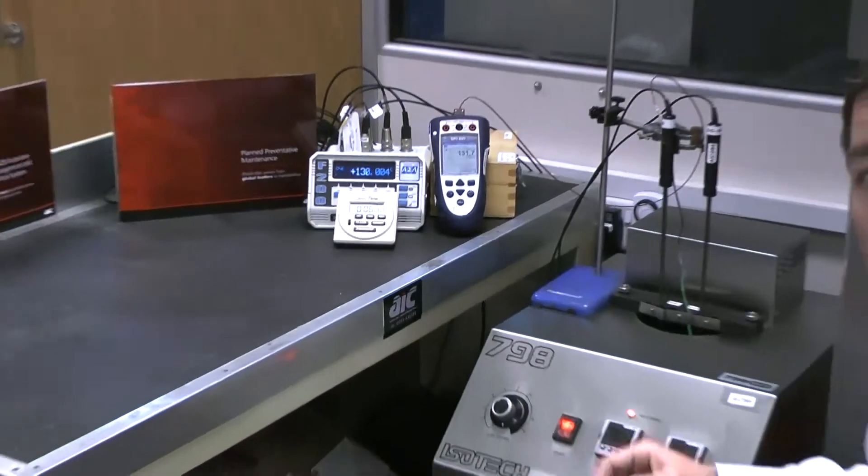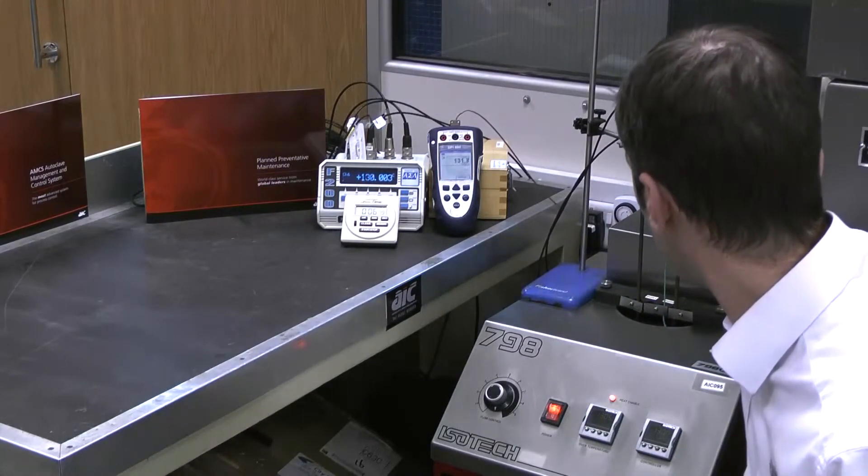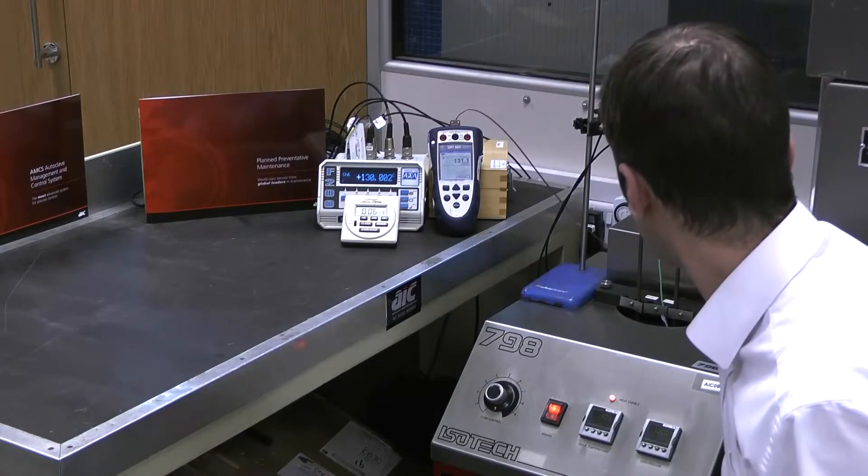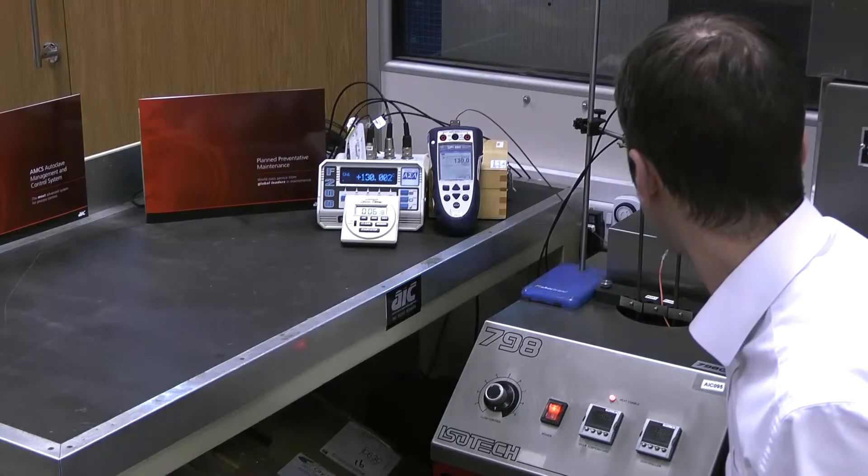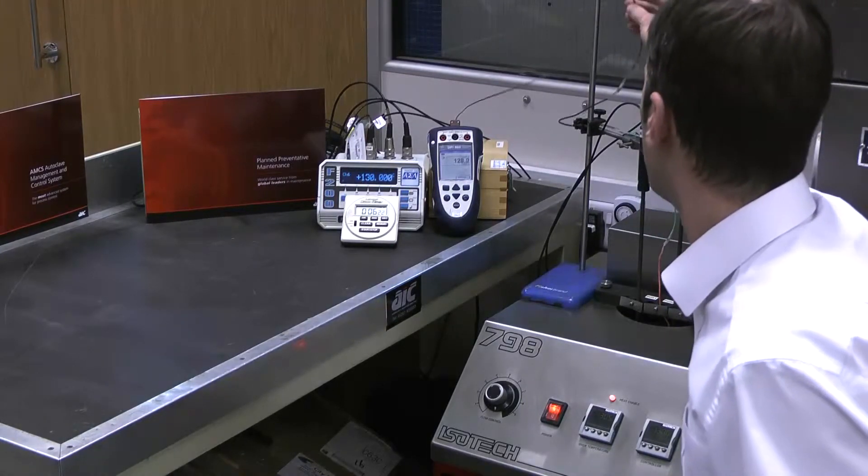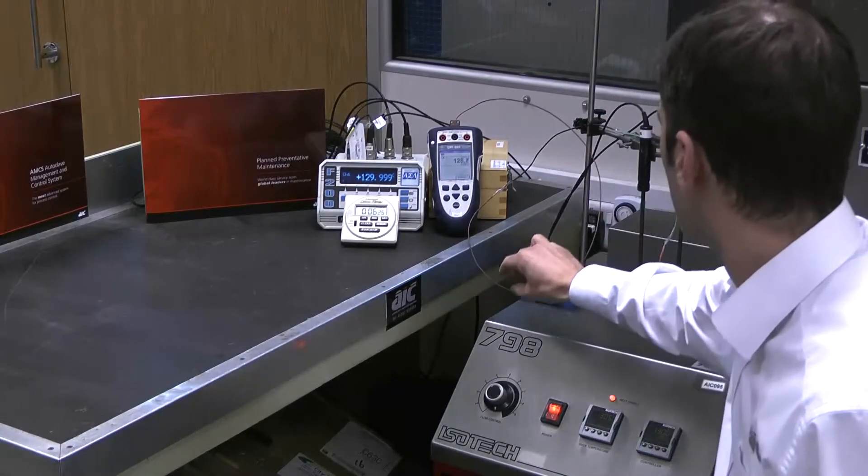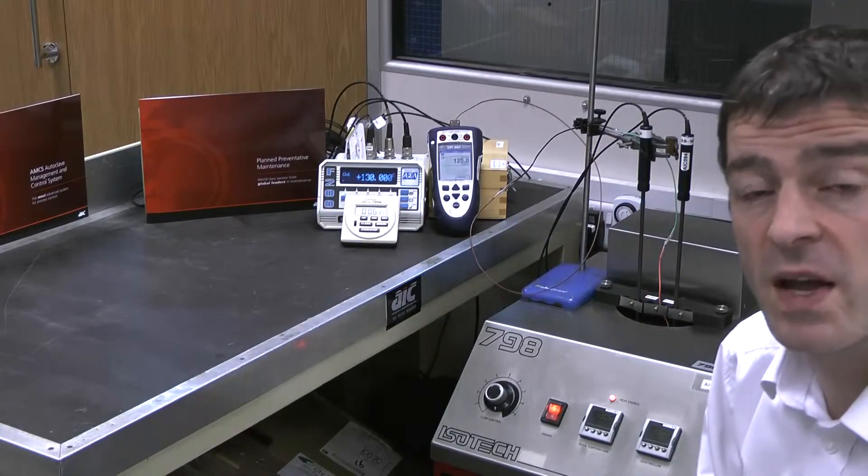And last of all, we pull the Type K thermocouple out further, and we get to Type N, pull it out here, and it's out of the way.